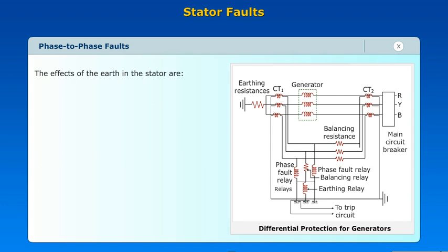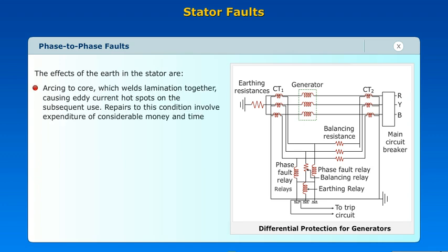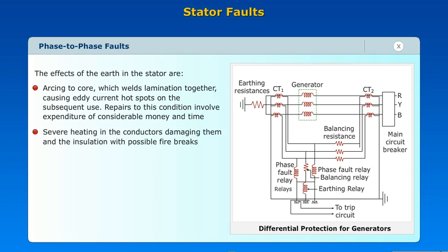The effects of earth faults in the stator are arc into the core, which welds laminations together causing eddy current hotspots on subsequent use. Repairs to this condition involve expenditure of considerable money and time. Severe heating in the conductors damages them and the insulation, with possible fire breakouts.